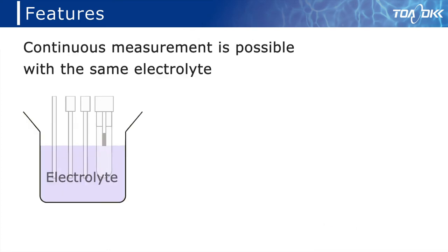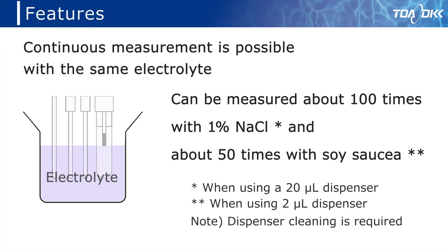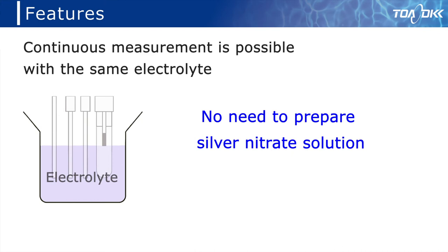The fourth feature is that continuous measurement is possible with the same electrolyte. It is possible to measure about 100 times with 1% NaCl and about 50 times with soy sauce. There is no need to prepare a silver nitrate solution for manual analysis. In addition, the amount of waste liquid can be reduced.